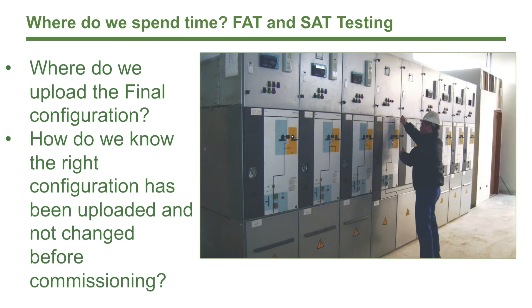I mean, we still load the final configuration, we still secondary inject every IED during the SAT, and we still apply telecontrol point-to-point tests for the substation gateway and the SCADA system. I mean, how could we possibly know that the configuration that has been loaded and tested by the system integrator is the same configuration that has made it through commissioning?